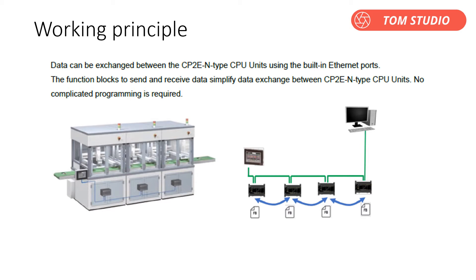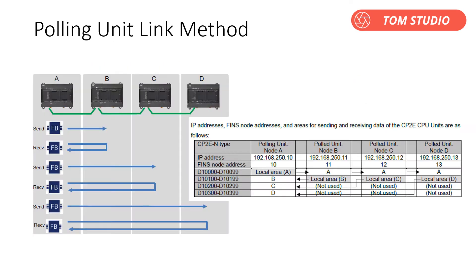No complicated programming is required. A maximum of one CP2E can communicate with up to three other CP2E CPUs, because the FINS protocol in micro PLCs has a three-device limitation when using TCP protocol — please be aware of that. This is called the polling unit link method, and as shown in the example, you can easily use function blocks to implement data exchange between PLCs.